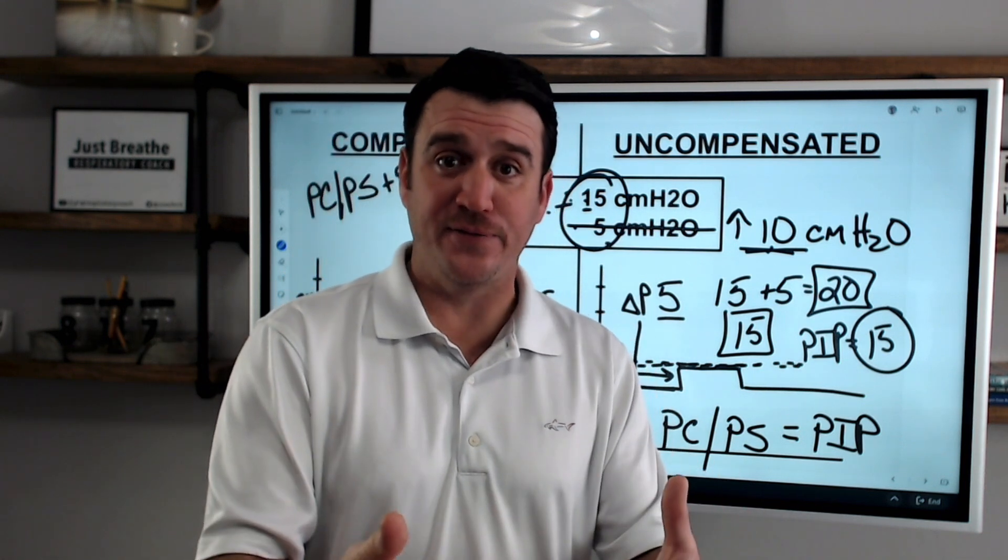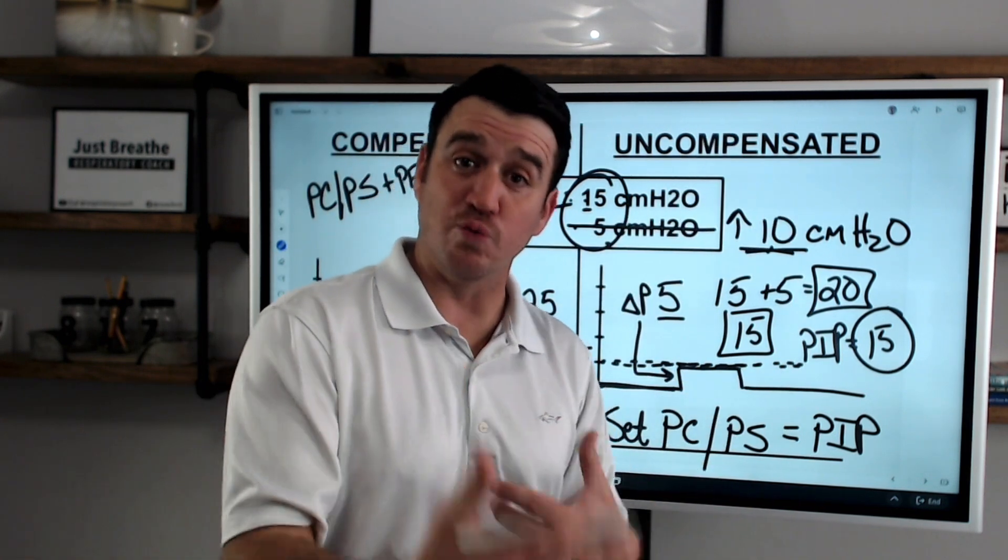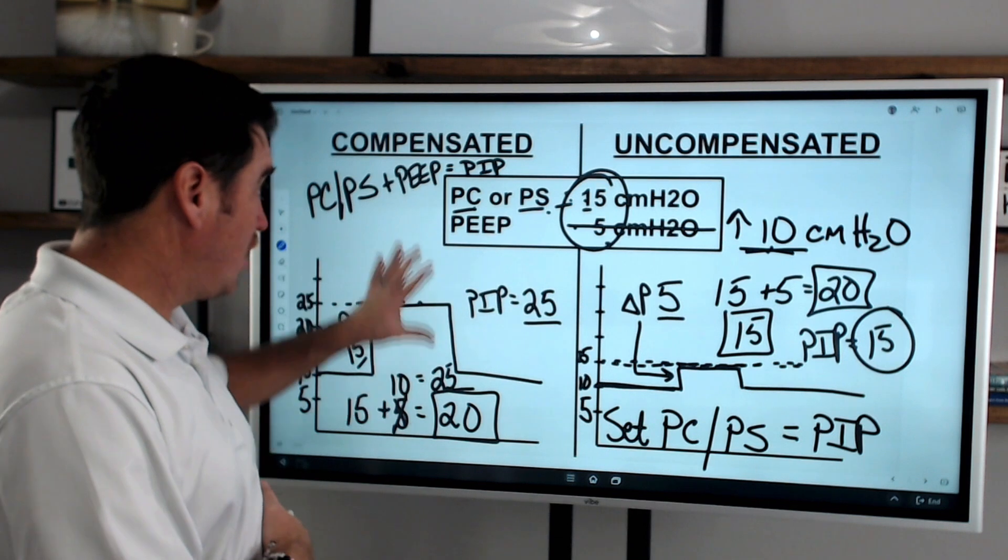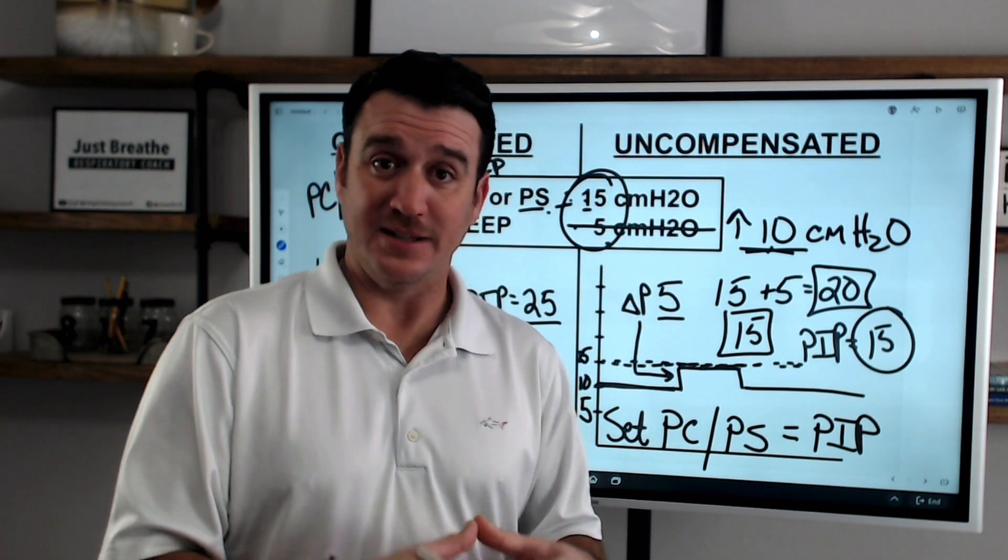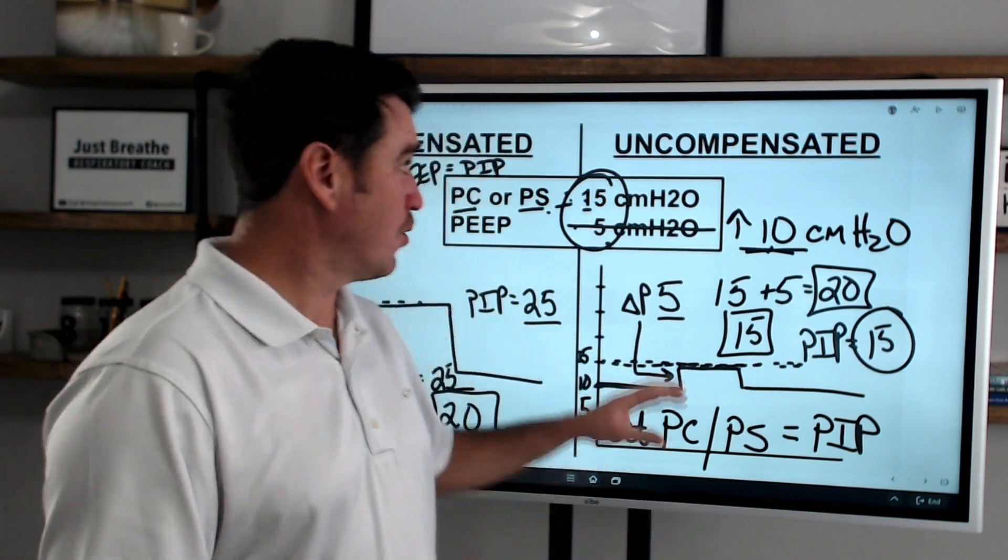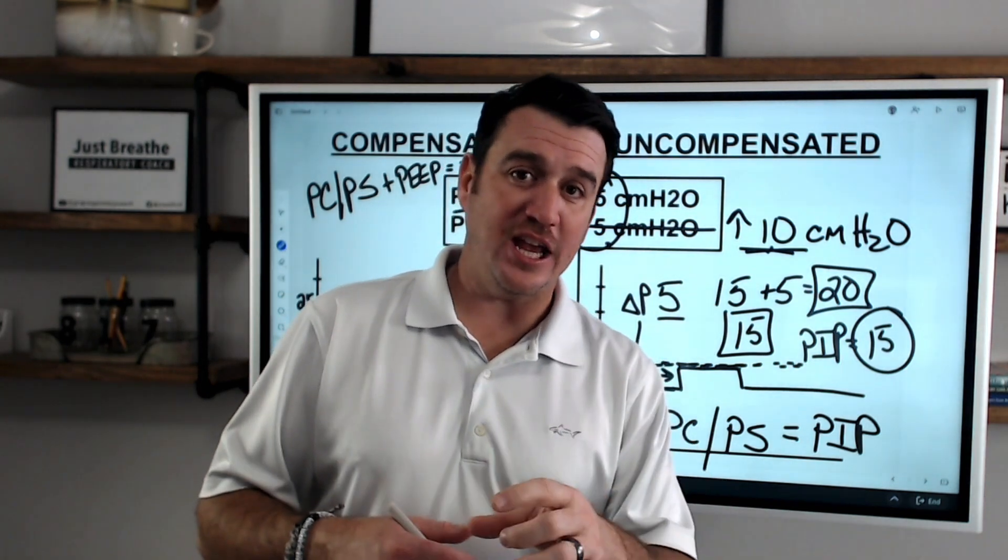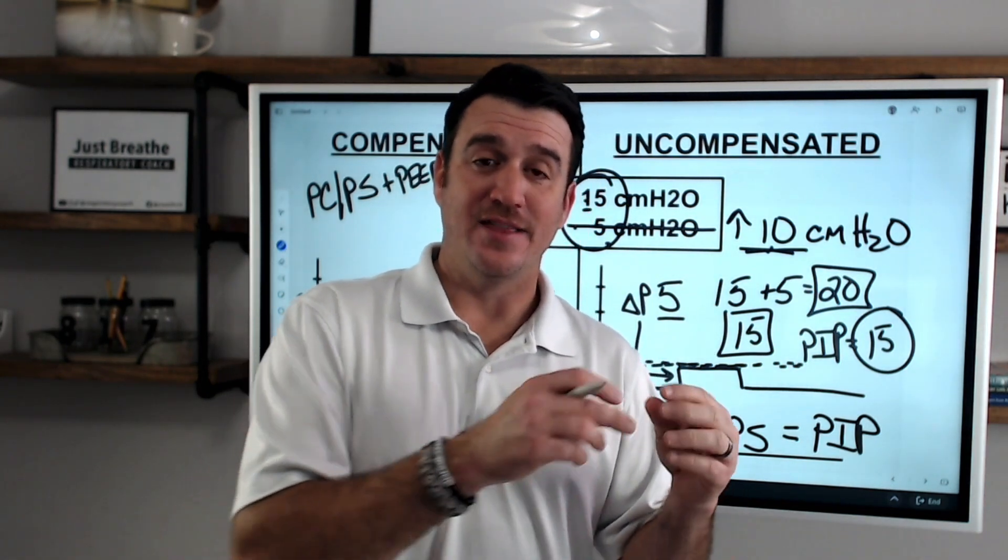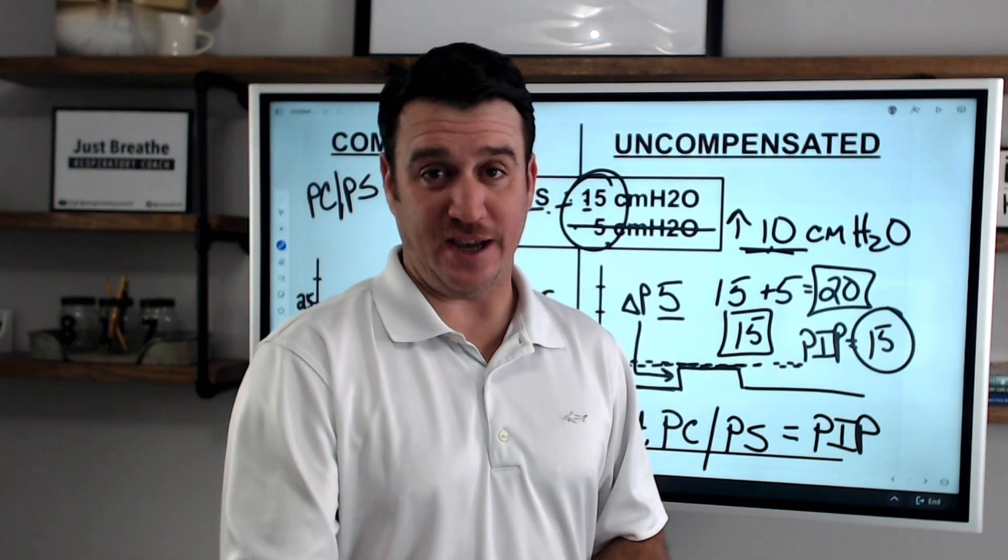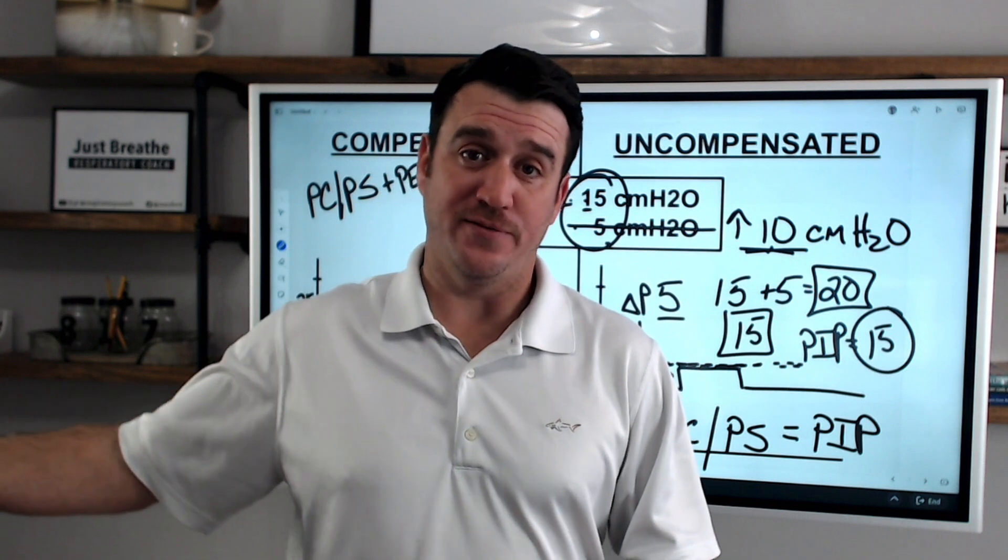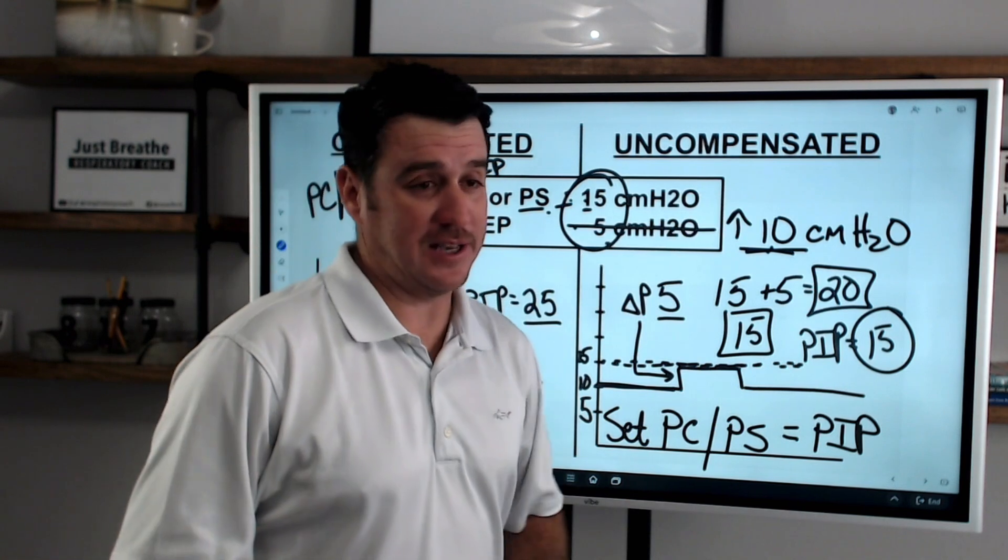Now, if you are used to working with an uncompensated ventilator, then you need to recognize when you walk into the realm of a compensated ventilator when it comes to PEEP. This is very important because when you're working with uncompensated ventilators, any change in PEEP will affect the delta P, which will affect your delivered tidal volume and ultimately affect your minute ventilation. So that's compensated versus uncompensated.